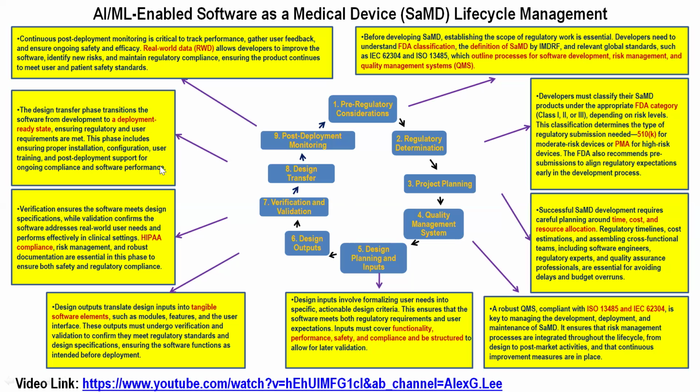And also you have an AI/ML enabled component. On the FDA side, they are very recently interested in when an AI/ML component is included in a medical device. What happens is that the AI/ML is continuously running. For example, you have a targeted initial use case, and then you get the FDA clearance. But after approval, your AI can improve using new data and new training, and it can change many things, right?